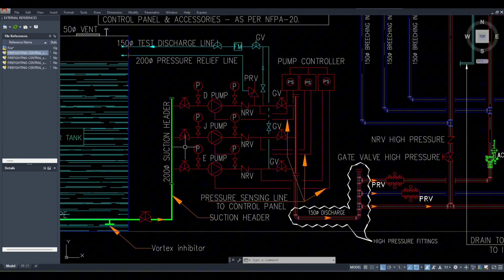Then if you are at the shop drawing stage or construction stage, you need to verify the length and width of this pump - how much space it really takes. From the catalog you'll find the actual dimensions of these pumps, then check it. Since this is a schematic you'll do on the floor plan, you need to see how long it is taking.